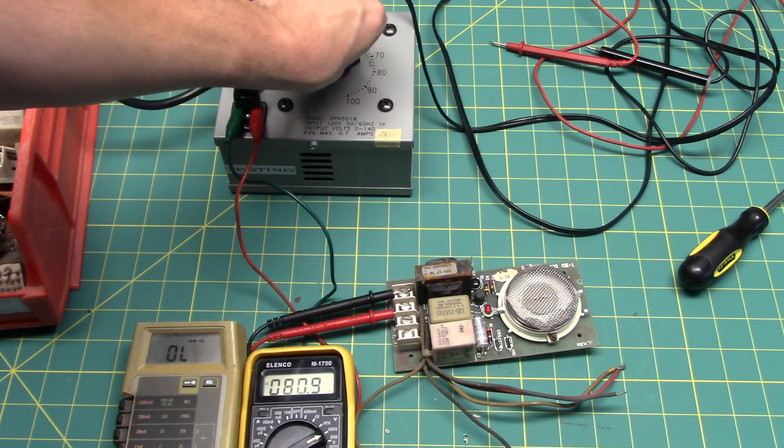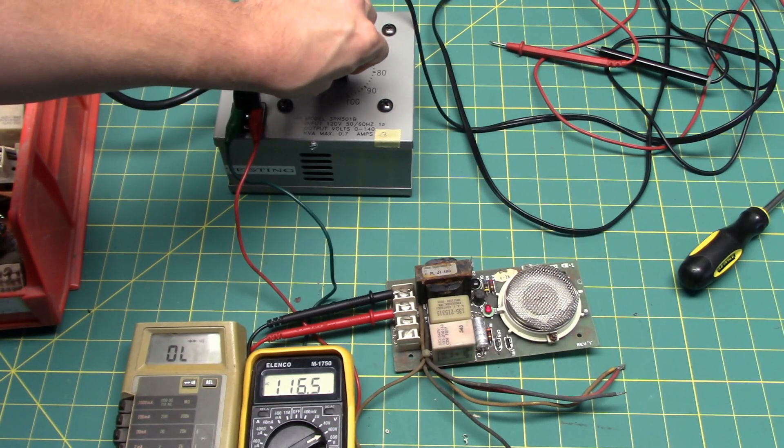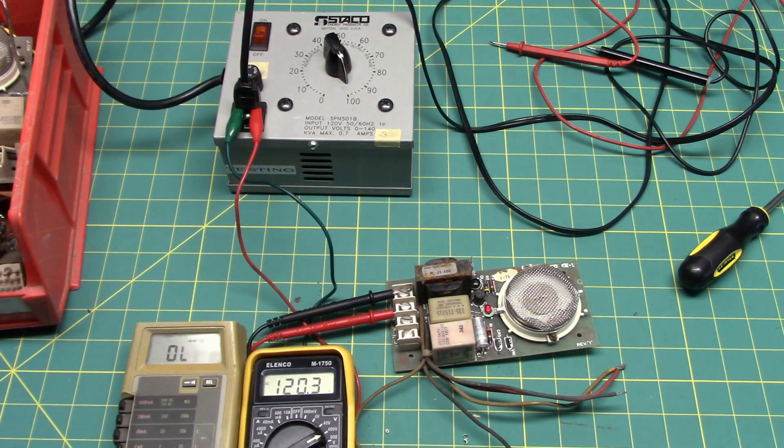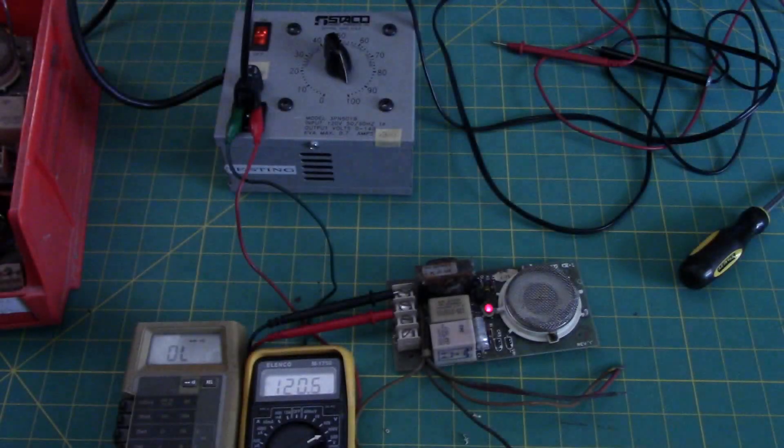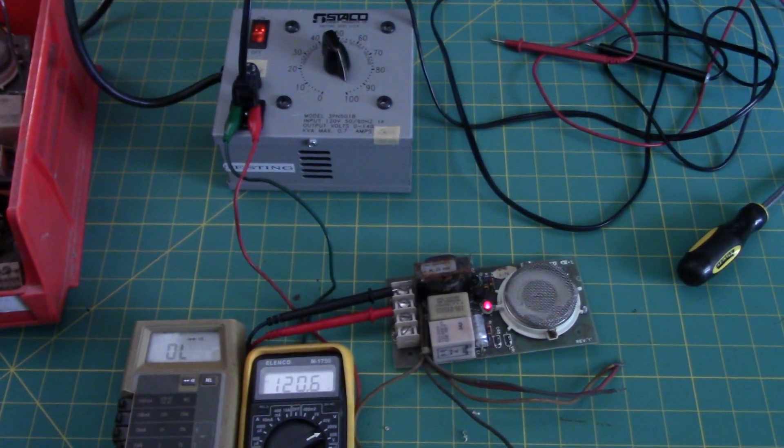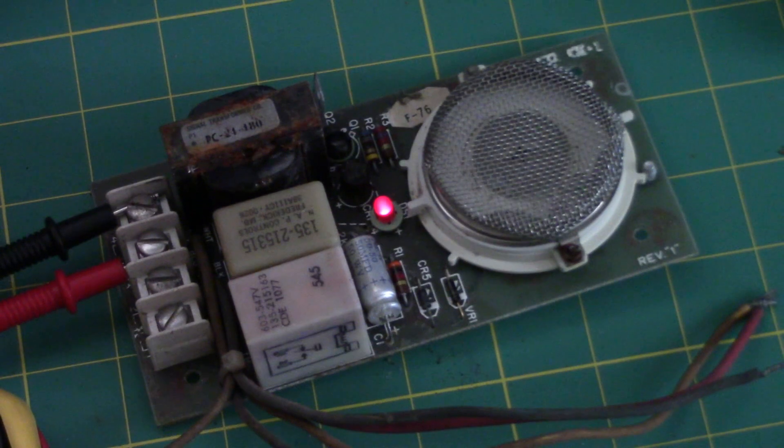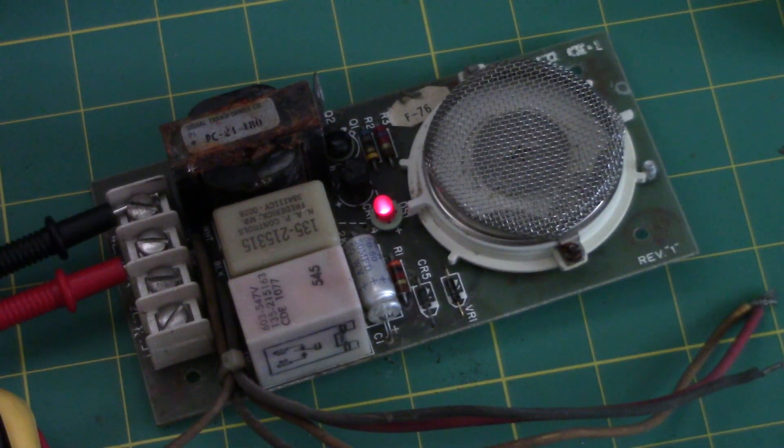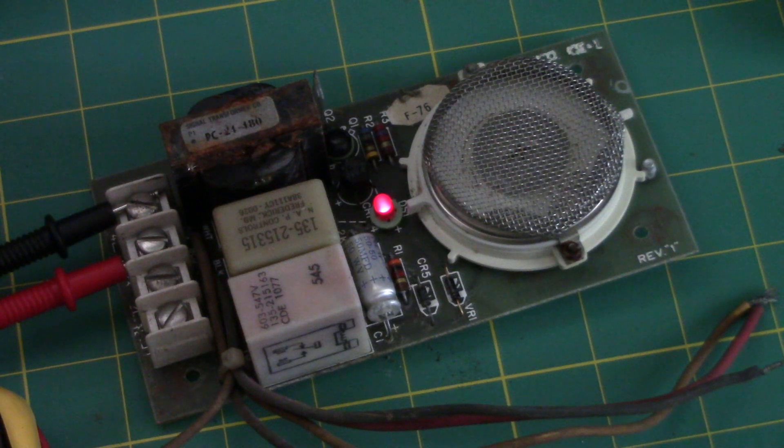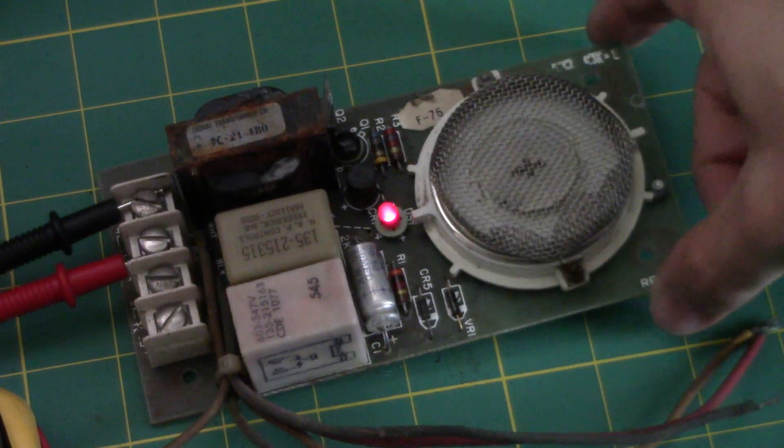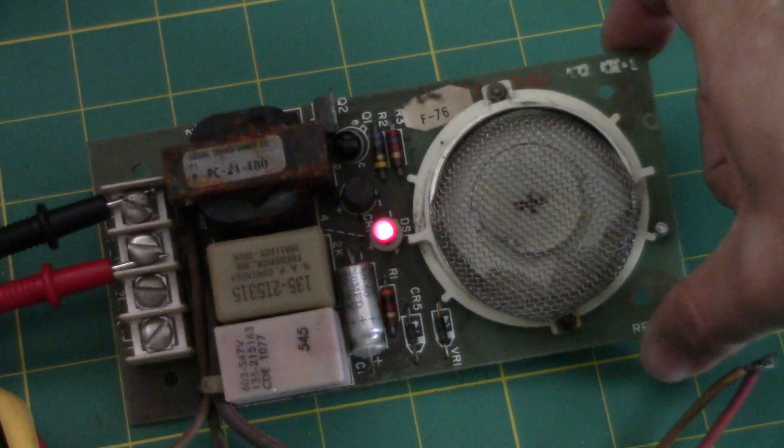You notice the LED begins to light on the detector. The smoke detector runs at about 25 volts, 24, 25 volts DC when you have 120 volts AC in. I'll turn off this overhead light so you can better get a glimpse of the LED lit up. So the LED does not detect smoke. The LED does not indicate smoke being detected. The LED merely indicates that there is power applied to the smoke detector.